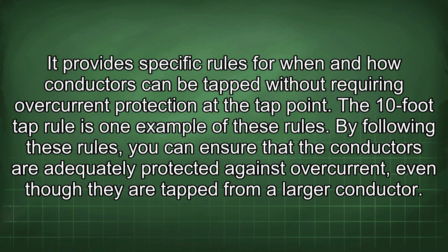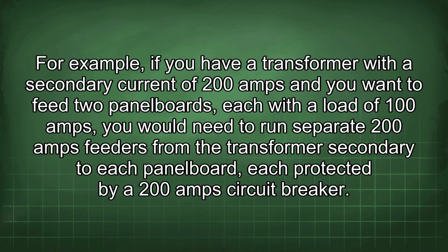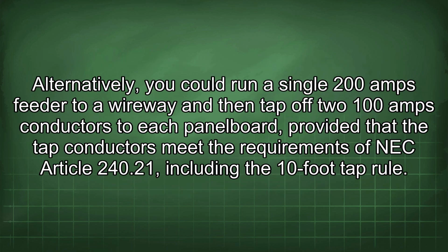from a larger conductor. For example, if you have a transformer with a secondary current of 200 amps and you want to feed two panel boards, each with a load of 100 amps, you would need to run separate 200 amps feeders from the transformer secondary to each panel board, each protected by a 200 amp circuit breaker. Alternatively, you could run a single 200 amps feeder to a wireway and then tap off two 100 amps conductors to each panel board, provided that the tap conductors meet the requirements of NEC Article 240.21, including the 10-foot tap rule.